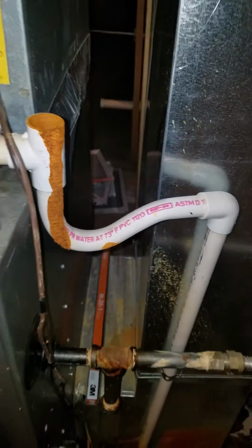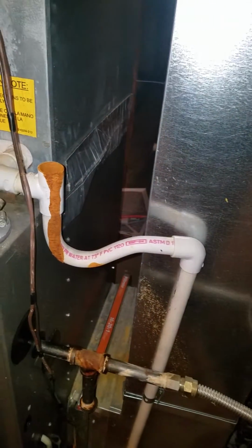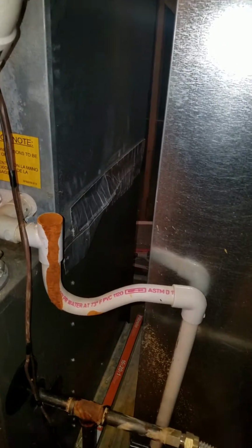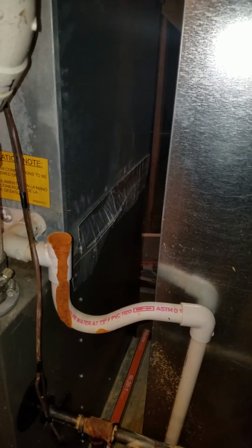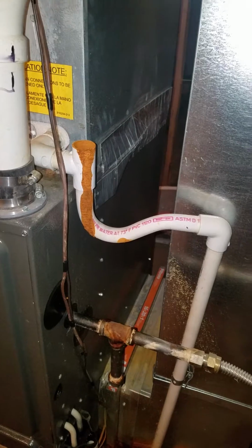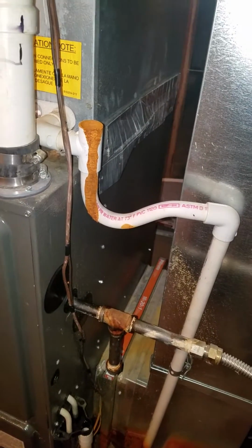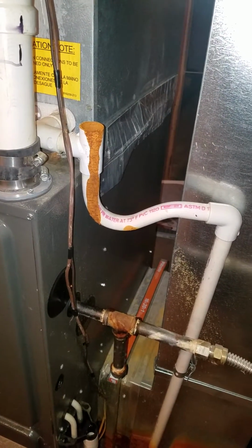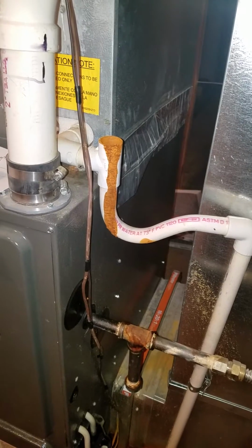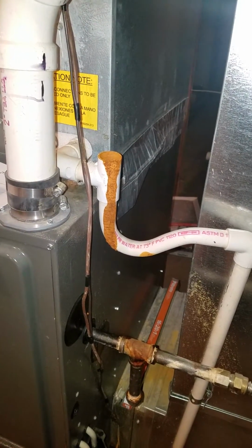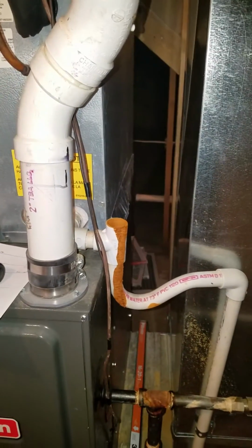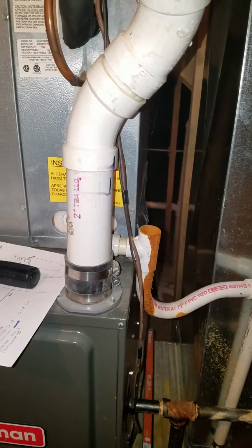There's already been some damage inside this coil and severe rust, and what has happened is this has leaked in and over the heat exchanger, and that's where the rust inside the heat exchanger right now is taking its toll on the heat exchanger. So that's the issue, and possible fracture in the heat exchanger.